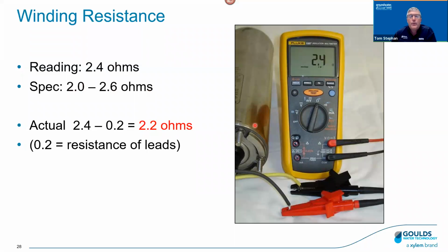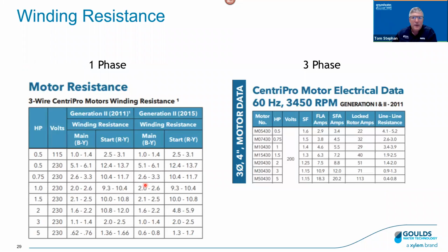And so we can see here the example is I've got the motor on my test bench and certainly no power, right? So I'm measuring ohms with my meter and I get 2.4 between the yellow and the black. I looked that up in those books and the spec says you should be getting between 2 and 2.6. Well, the tricky thing about these meters is there is some resistance in the wires, which is about 0.2, not a huge deal. But if I subtract that, I'm at 2.2, so I'm right within the specification of that motor. The nice thing about that book is that it tells you exactly what it means if it's low, and what it means if it's high.